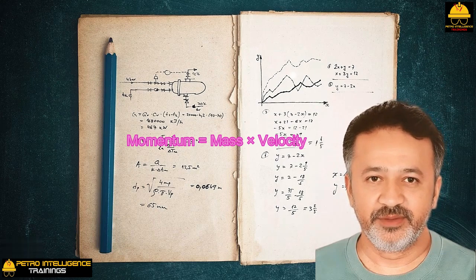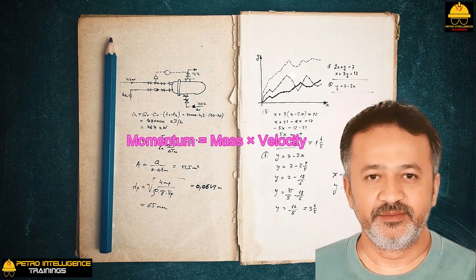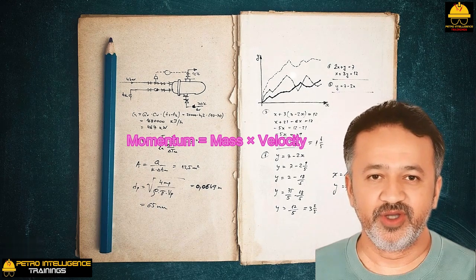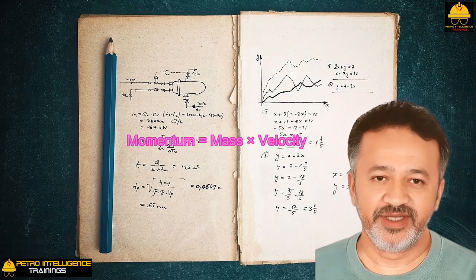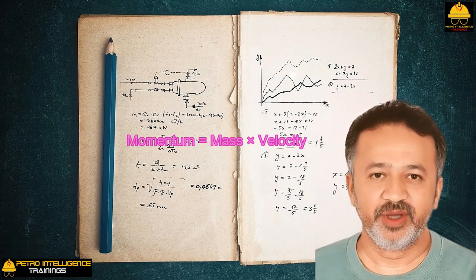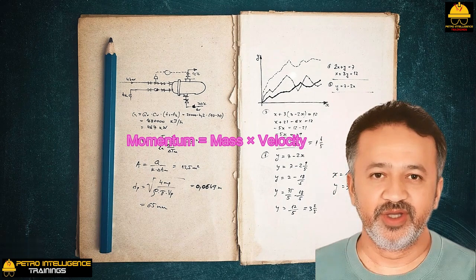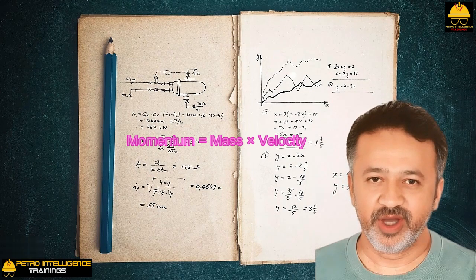You can see quite clearly that it is not the pressure of the steam that is driving a turbine. Place a pressure gauge on the turbine case of a single wheel machine. The pressure on the turbine case will be quite close to the exhaust steam pressure and certainly not the motive steam pressure.